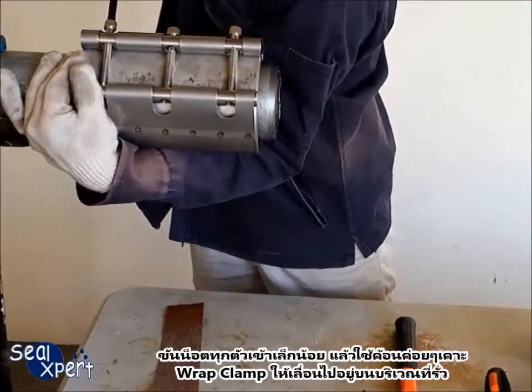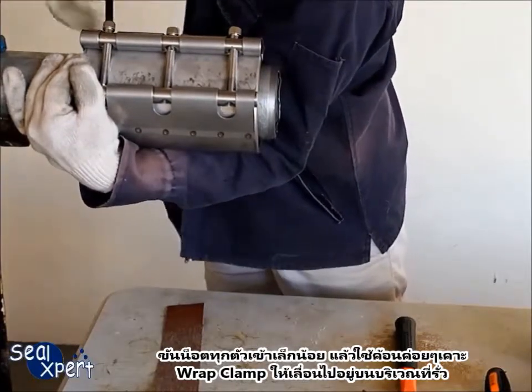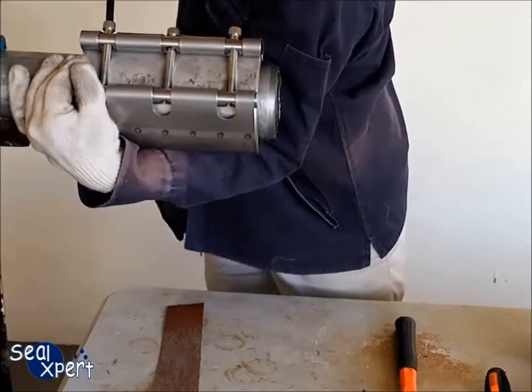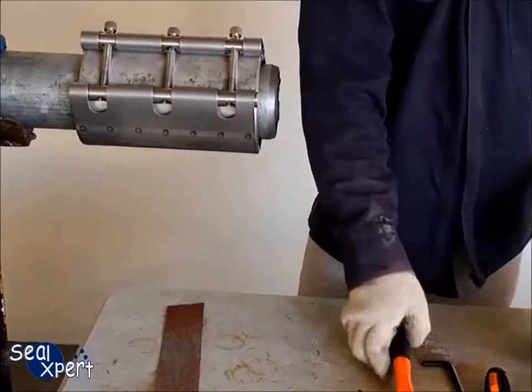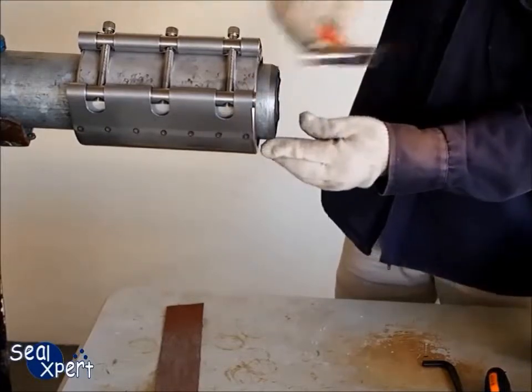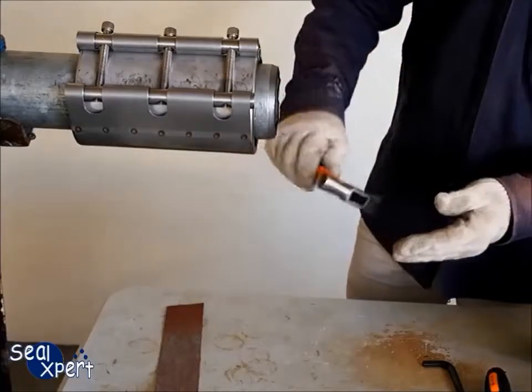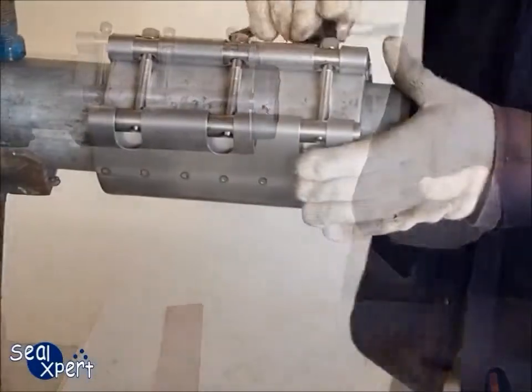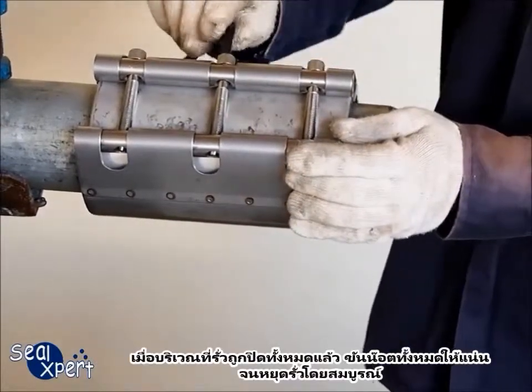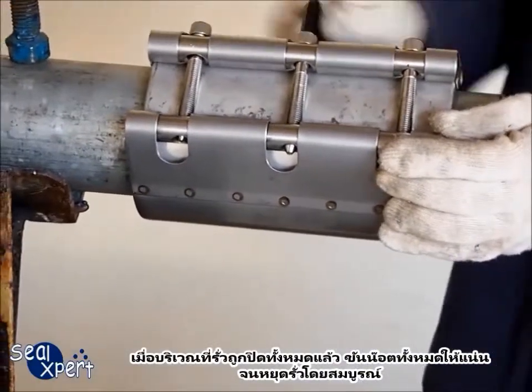Tighten all the bolts slightly and gently hammer the Wrap Clamp so that it glides over the leak area. Once the leak location has been covered completely, tighten all the bolts until the leak is stopped completely.